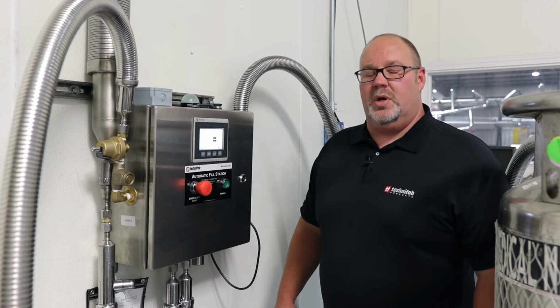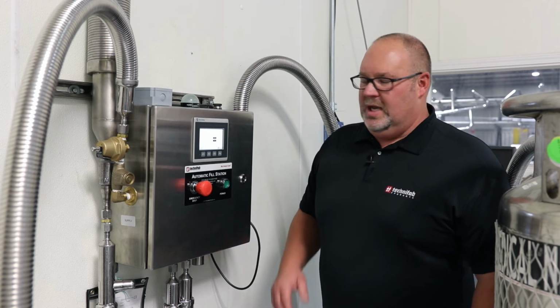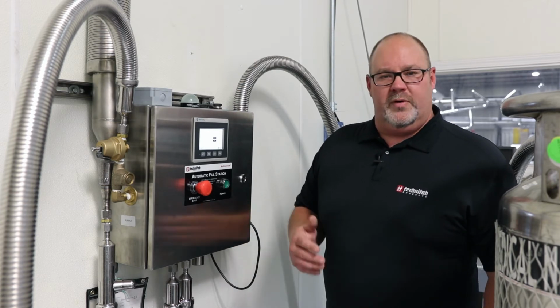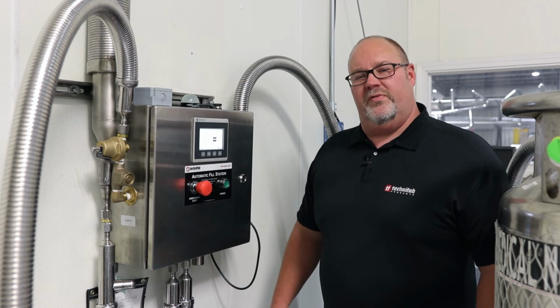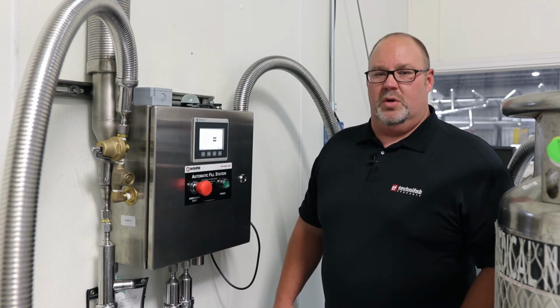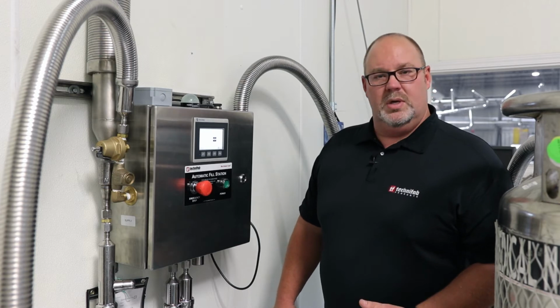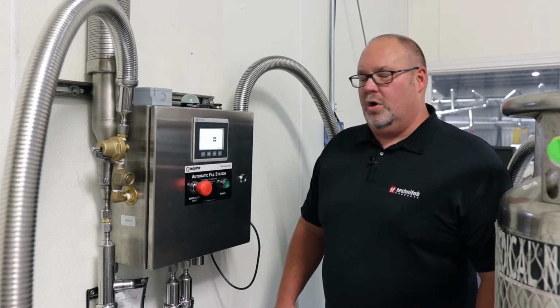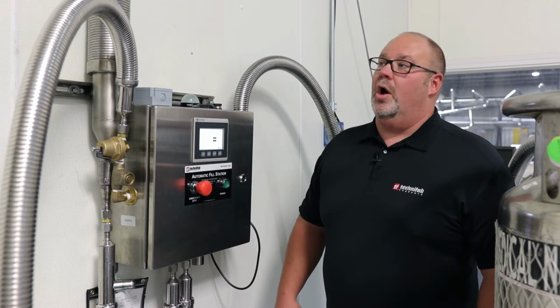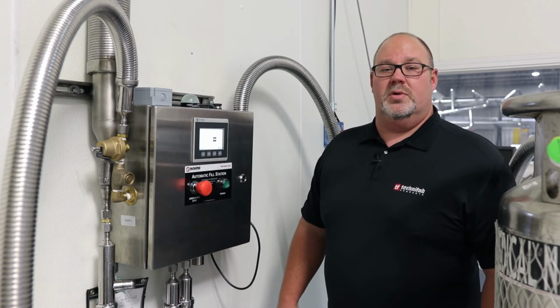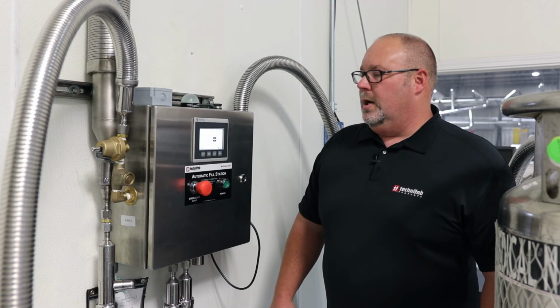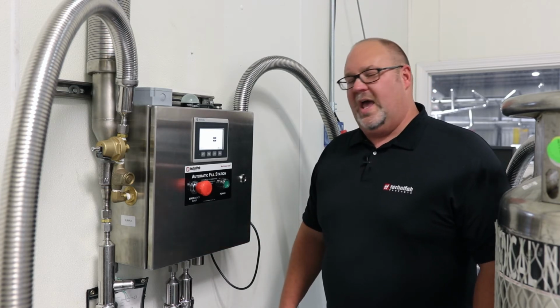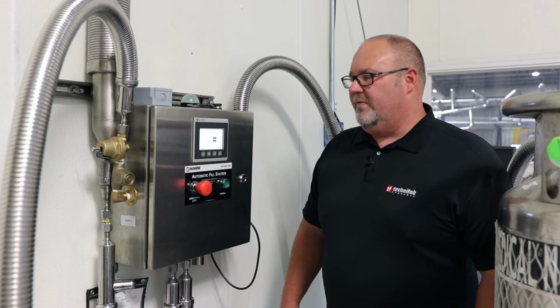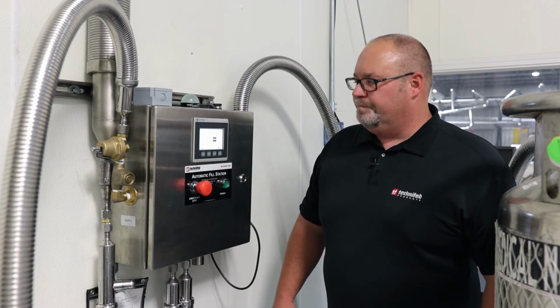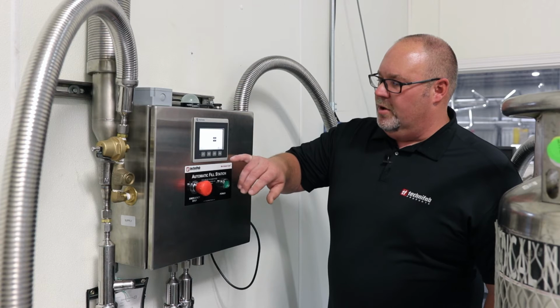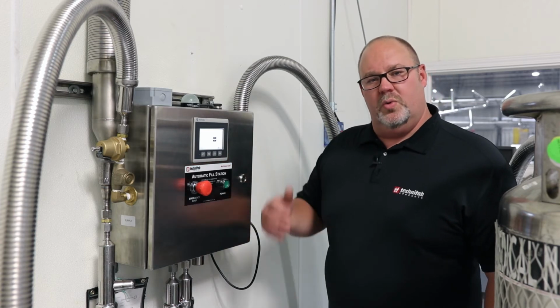Timeout timer is also another safety feature. It's how long it takes your unit to fill from start to finish, so that it does not continue to fill if somebody walks away or if there's some sort of a failure in the system. As I said, it is set at 75 minutes currently. You can adjust that based on the fill time or the pressure associated with your bulk tank, or depending on if you're bringing in tanks that are half full or quarter full, they may fill at a different time accordingly. So these can be adjusted, and in your user's manual, there's a way to walk you through how to adjust those.